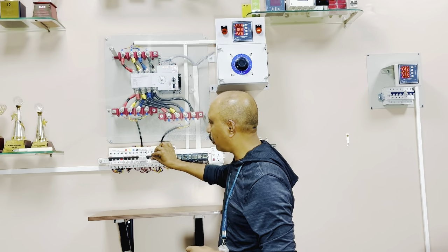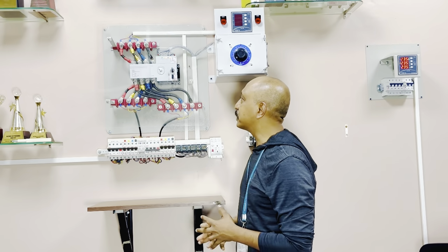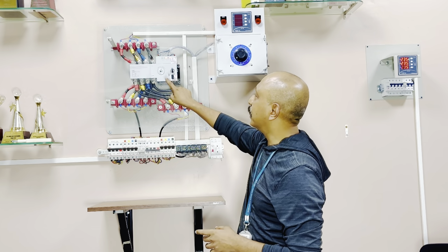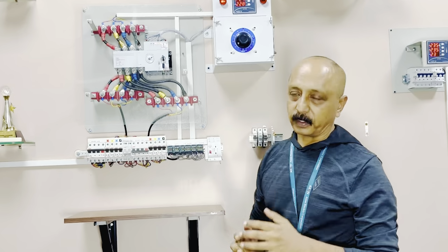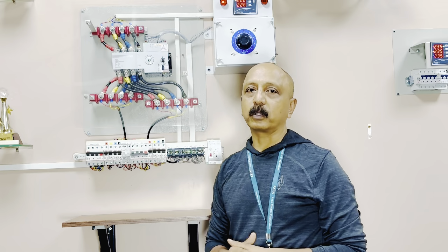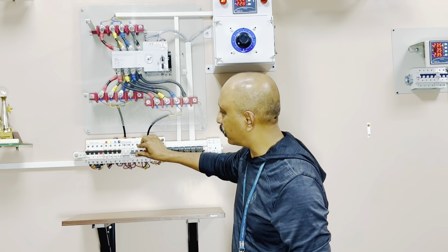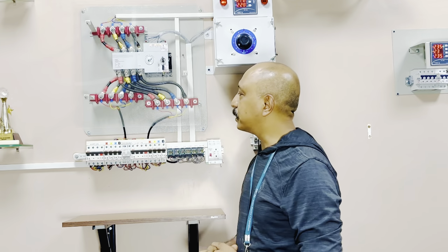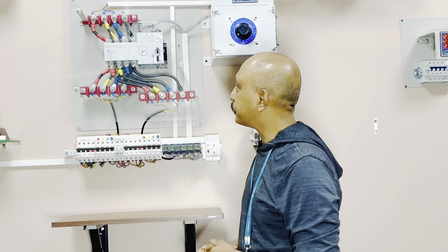We are now switching off the source 1 EB supply. The ATS senses that there is a failure of EB. Since the generator supply is available, it moves into generator mode. This is a simple function of auto transfer. Let's now understand how our auto recovery works. Let's assume that the EB has come back, so I'm switching on the EB supply. The moment the EB supply is on, the ATS recognizes that the supply is available at the source 1 terminal, so it comes back to source 1, thus complying with auto recovery.